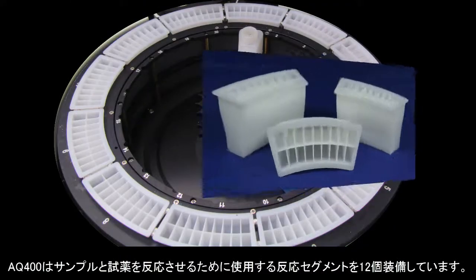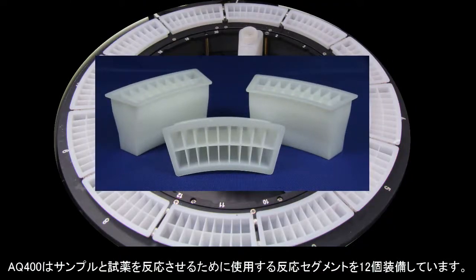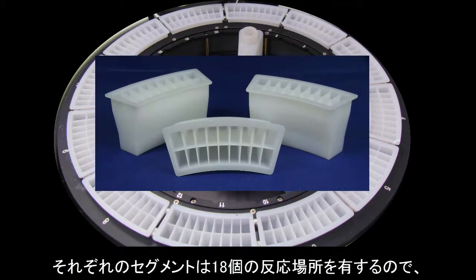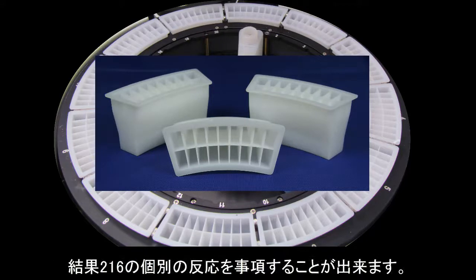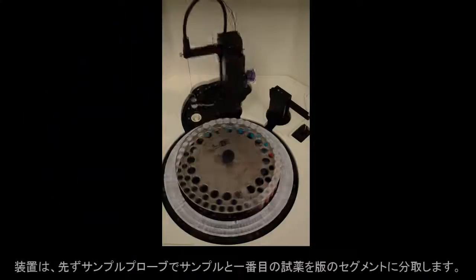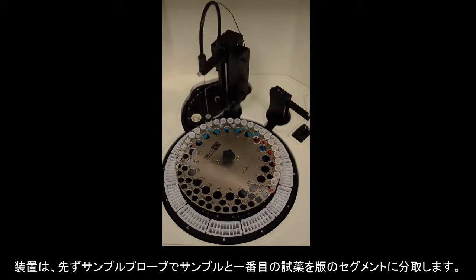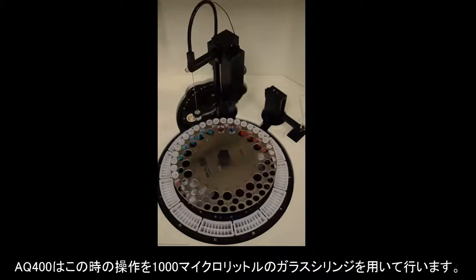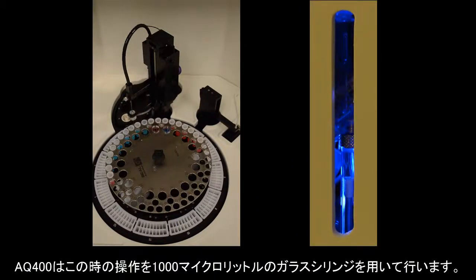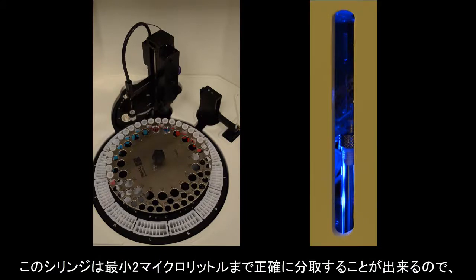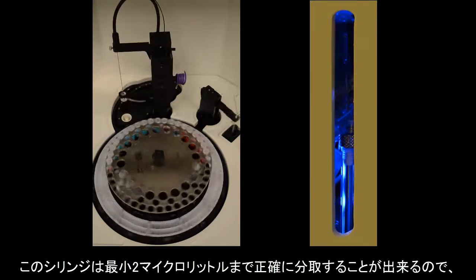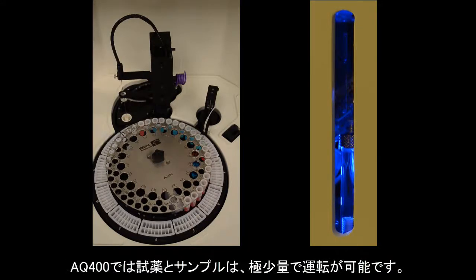The AQ400 holds 12 reaction segments that are used for the preparation of the reactions. Each of these reaction segments has 18 wells. Therefore, the AQ400 can perform 216 individual discrete reactions before anything needs to be replaced. To prepare a reaction, the sample probe picks up samples and reagents and deposits them into a reaction well. The AQ400 does this by utilizing a 1,000 microliter displacement syringe. This displacement syringe is capable of accurately outputting as little as 2 microliters, which is why the AQ400 is able to work with such small volumes of sample and reagent.